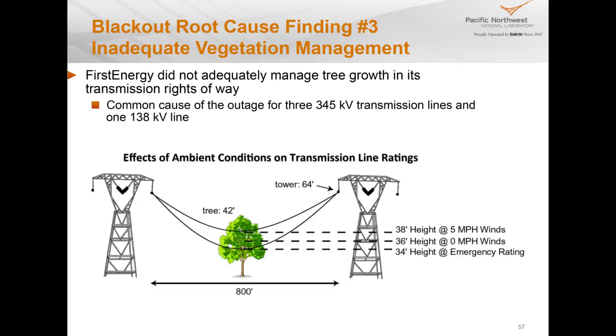Root cause number three was inadequate vegetation management. One thing we looked at was that on that particular day there was very little wind, and utility industry standard practice is to assume 2 feet per second of wind speed to cool the overhead lines when rating a transmission line. 2 feet per second is roughly 5 miles an hour, so you assume a little breeze to cool the line. At that time, when all these lines were tripping, the Akron airport was reporting 0 knots of wind. So we thought maybe our whole practice of rating lines wasn't right, but we ran the numbers, and it was just a few feet of difference between 0 and 5 miles an hour.